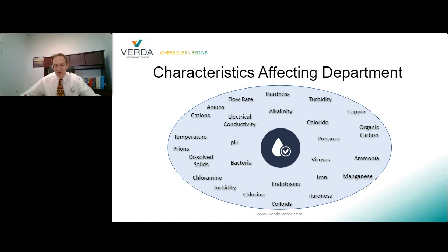If you're only checking your pH and chlorine monthly or annually, you might be producing elevated chloride levels in your final rinse and not even know about it until your next monthly, quarterly, or annual chloride test. Slight corrosion damage on your instruments might be the first clue that something's not right.